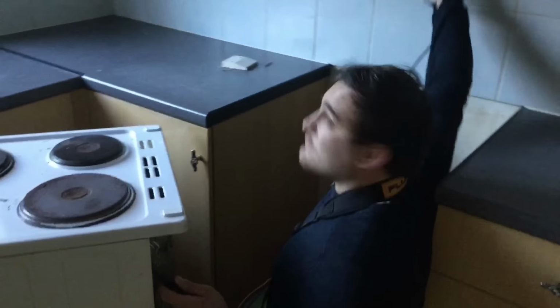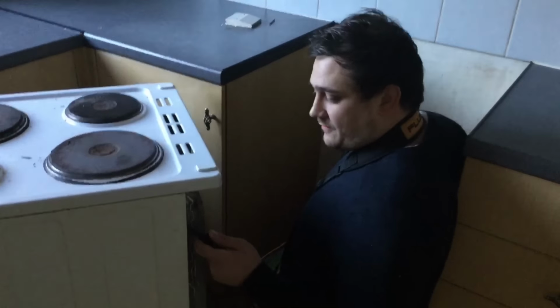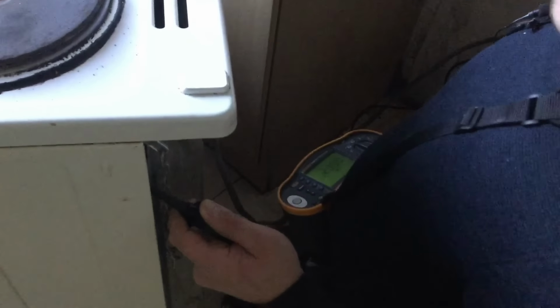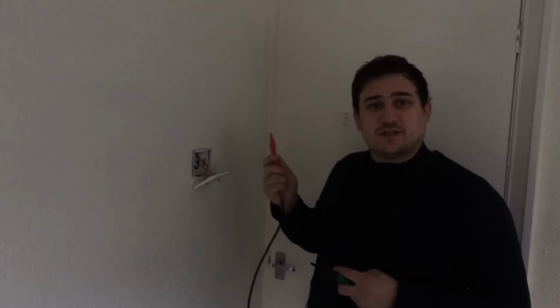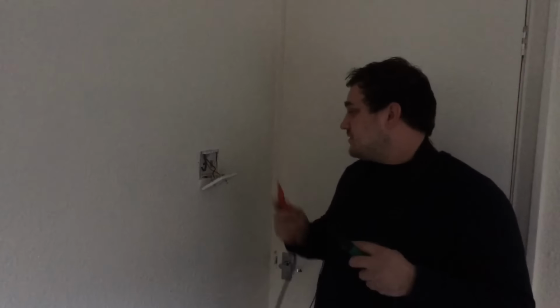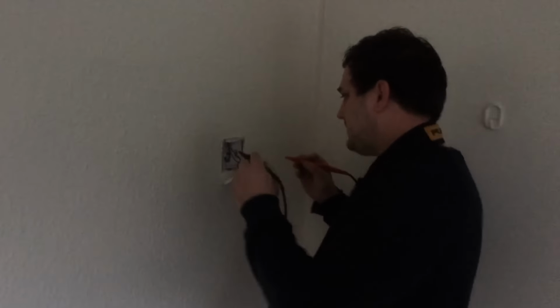Now to prove polarity, which is another dead test while I'm here, I'm going to flick off the cooker switch, probe back on, and now have an infinite reading. So carrying on from my continuity of my circuit protective conductor on the lighting circuit upstairs, I've worked my way around all the upstairs lights and switches, leaving the switches in the on position for the later insulation resistance test. I found my last point, which I also found in my pre-tests. So now I'm just going to test at the last point where we should obtain the highest reading.